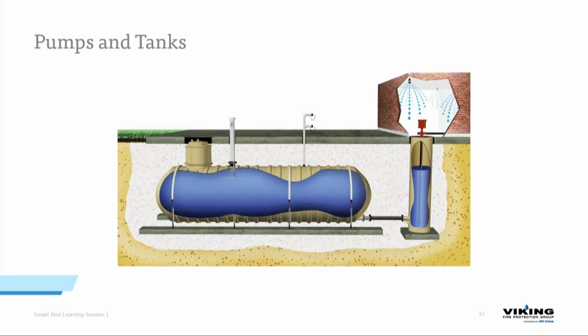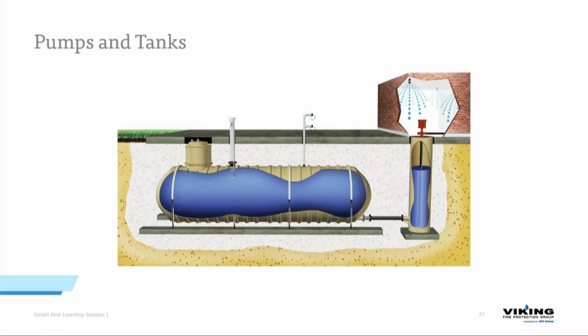We have a water level monitor. Again, these should be made electronic and be fed back to a control room or fire pump room. Don't want to depend on somebody walking out there and looking down there to make sure you have enough water. You need to know if there's a leak right away. Access tanks should be checked, cleaned, maintained. I know that does not happen a lot. Other considerations, anyone out there on the civil side: dead men, strapping, and very, very specific requirements for compaction and lifts. So I can tell you from experience that's not a fun experience for somebody who doesn't know civil. So those were some long conversations.